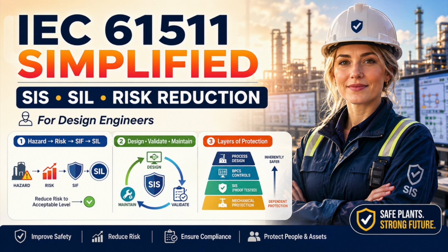A safety instrumented system is not safe because the logic solver is certified. It is not safe because you have redundant transmitters. It is not safe because the shutdown valve is tagged as critical. It is not safe because the project has assigned a safety integrity level. And it is certainly not safe because the design package contains a polished SIL calculation. Functional safety begins somewhere far less comfortable.